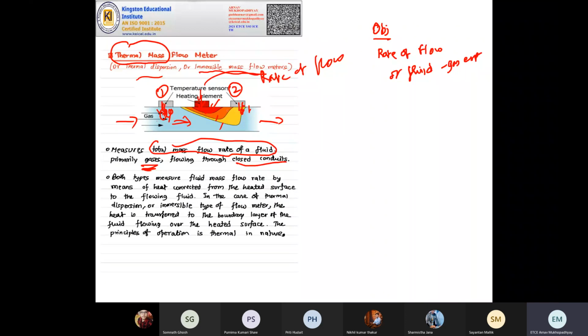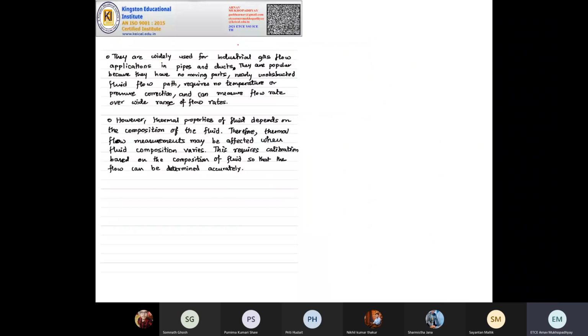There are two heaters. The heaters will heat up the gas that is flowing inside the conduit or the pipe. The faster the gas flow, the lesser will be the superheated area. This red area is the heated area, superheated. So the smaller the volume of the superheated area, the faster is the velocity or volume flow rate. You can calibrate it and then you can display it. This is the most popular industrial flow application in pipes and ducts. So it is the most important one, and the most popular one used in industry.